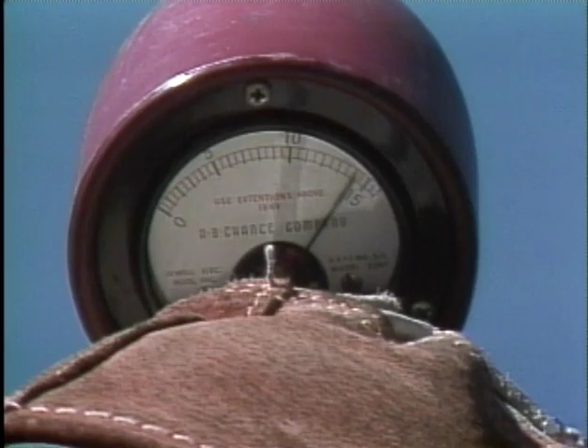You've seen how noisy testers, statiscopes, and phasing test sets confirm whether or not a circuit is de-energized. We also looked at some of the steps you need to take to ensure your tester gives you accurate results. In the examples we showed you, the circuits we tested proved to be dead. However, that won't always be the case when you're testing out in the field.